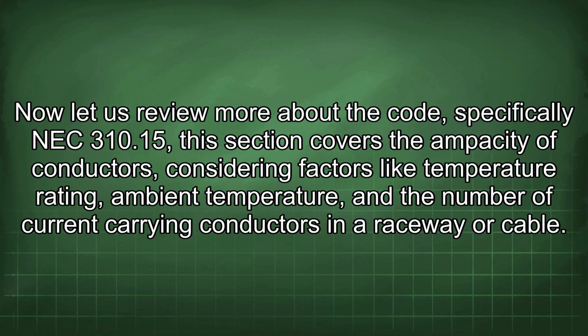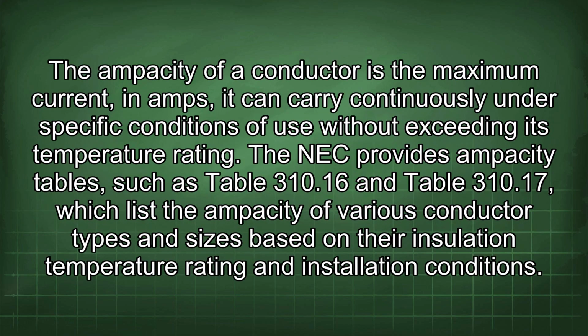Now let us review more about the code, specifically NEC 310.15. This section covers the ampacity of conductors, considering factors like temperature rating, ambient temperature, and the number of current-carrying conductors in a raceway or cable. The ampacity of a conductor is the maximum current, in amps, it can carry continuously under specific conditions of use without exceeding its temperature rating. The NEC provides ampacity tables, such as Table 310.16 and Table 310.17, which list the ampacity of various conductor types and sizes based on their insulation temperature rating and installation conditions.